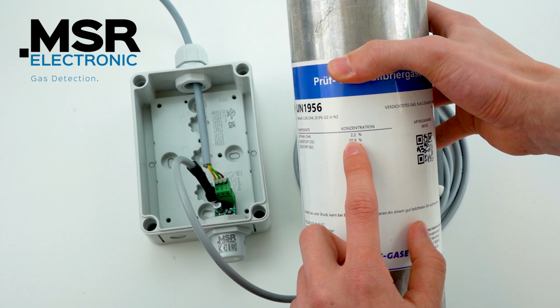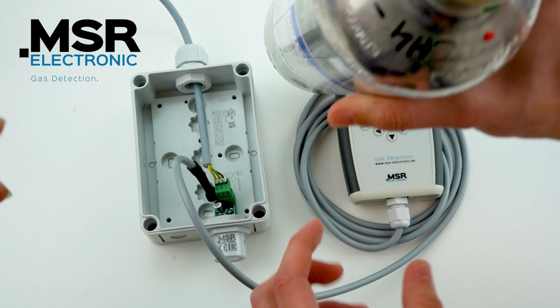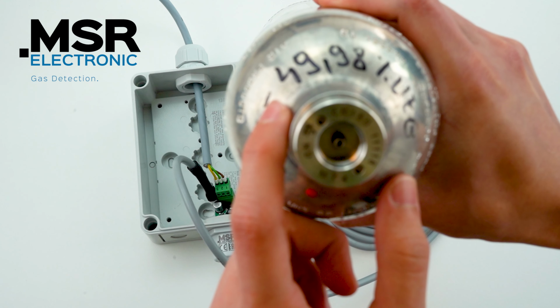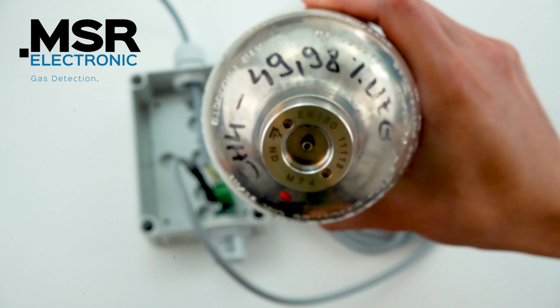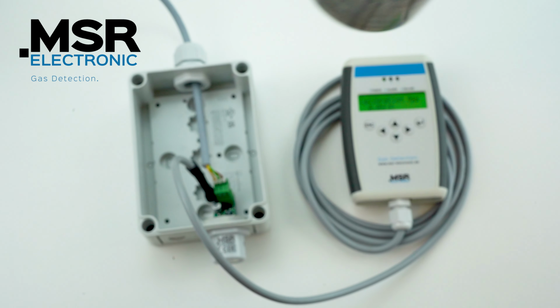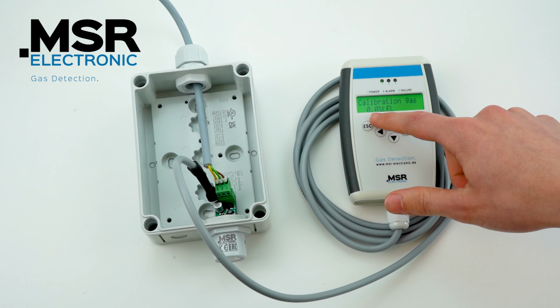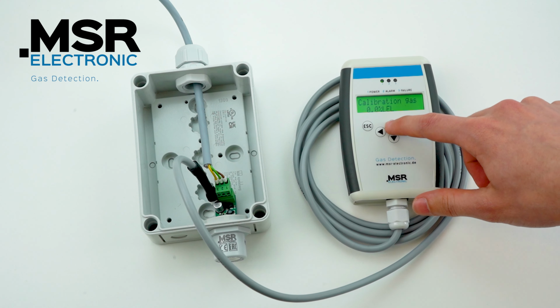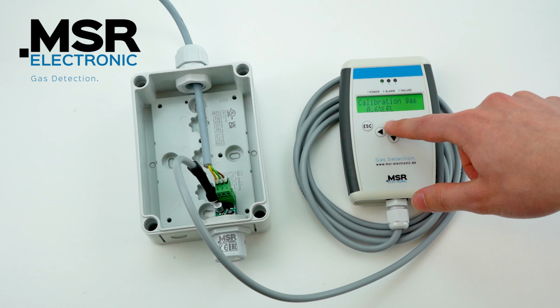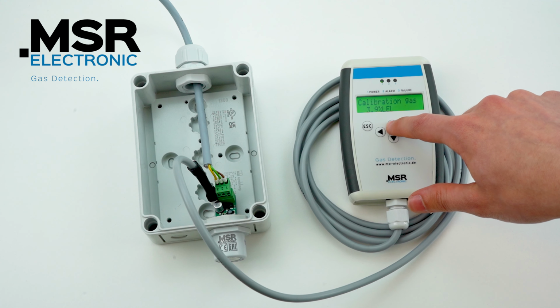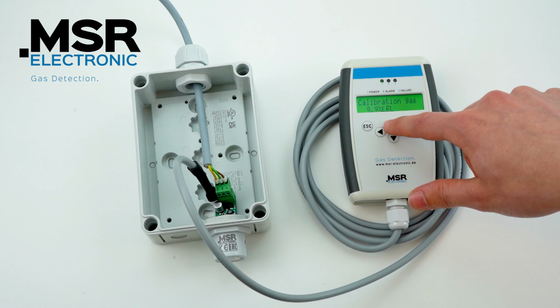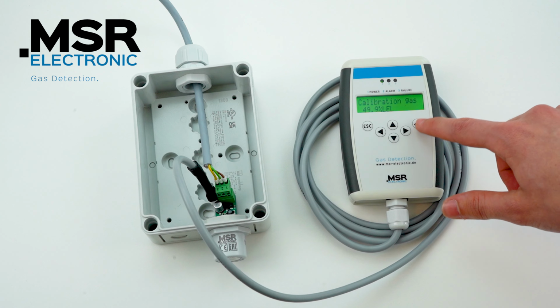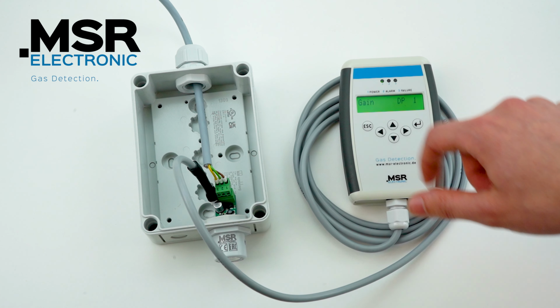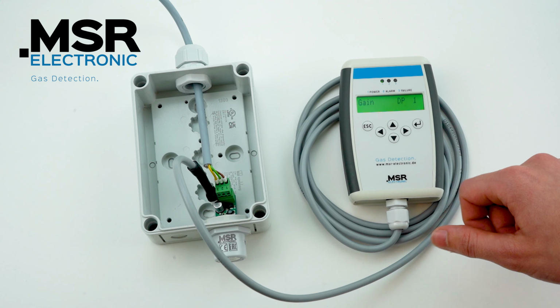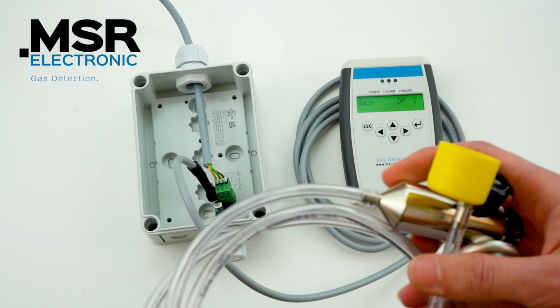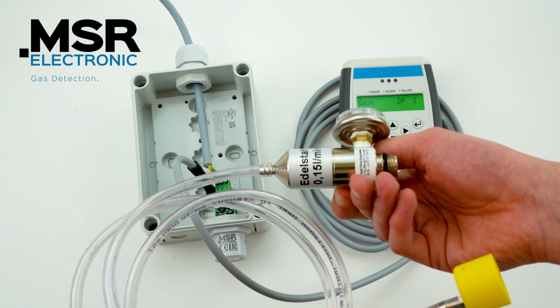The next step is to enter the test gas concentration. In my case, this is 50% LEL. Make sure that the test gas concentration is between 30 and 90% of the sensor's measuring range. Now the flow regulator can be mounted on the bottle and the sensor cap can be placed on the sensor.